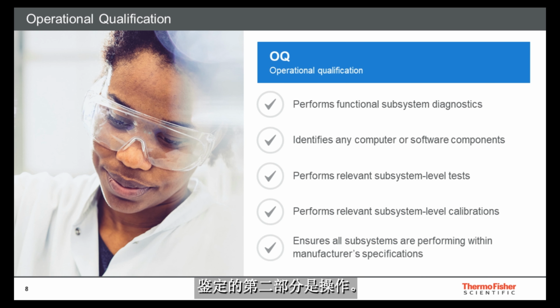Component 2 of the qualification is operational. By definition, the operational qualification will establish with confidence that process equipment and ancillary systems are capable of consistently operating within the manufacturer's established limits and specification tolerances. Additional supporting detail can be found in 820.72, Inspection, Measuring, and Test Equipment, 820.80, Acceptance Activities, and Subpart N of 820.200, Servicing, all in the Code of Federal Regulations.